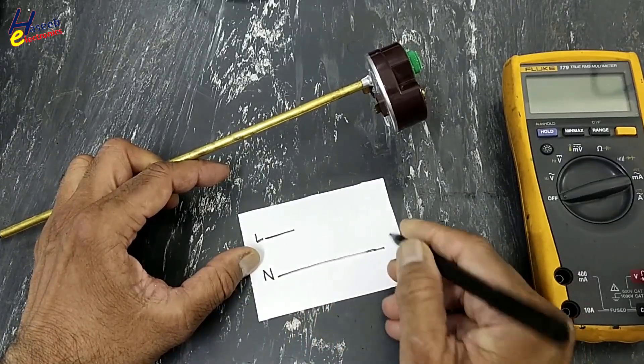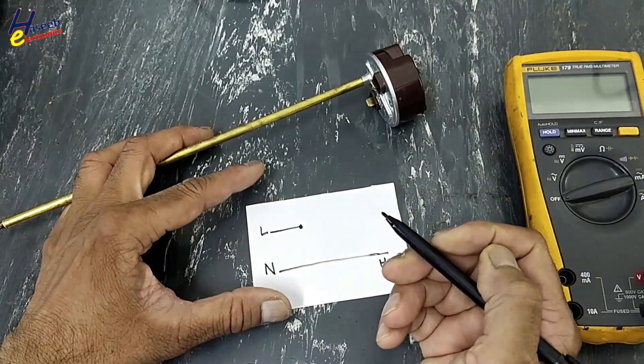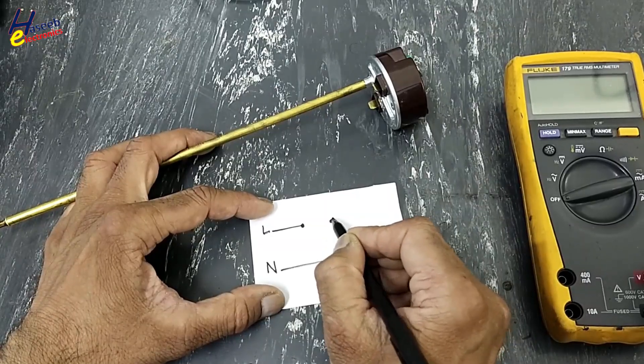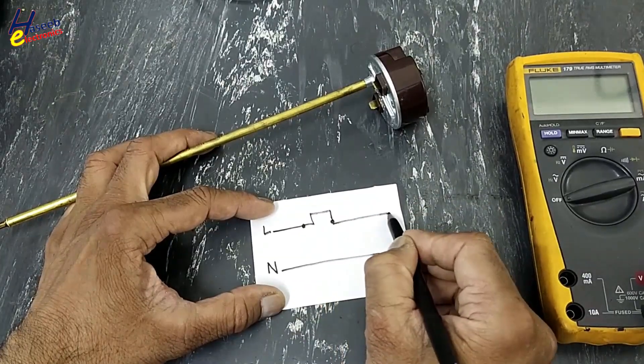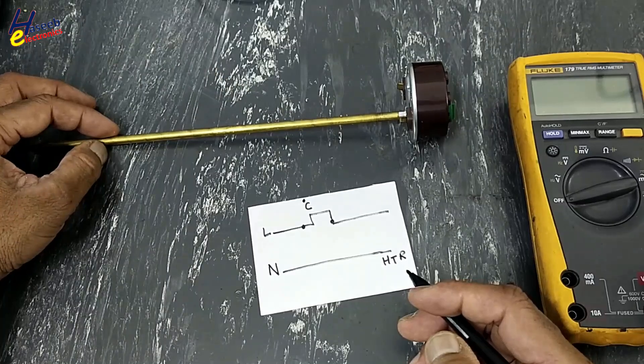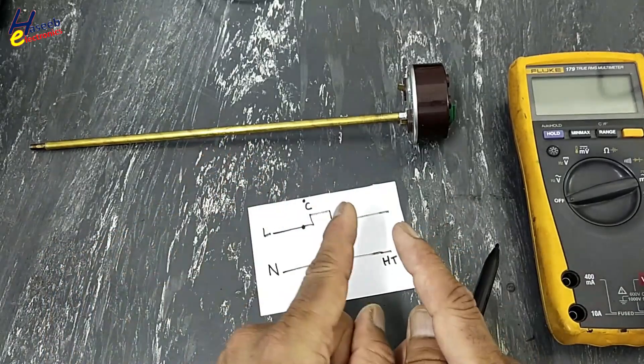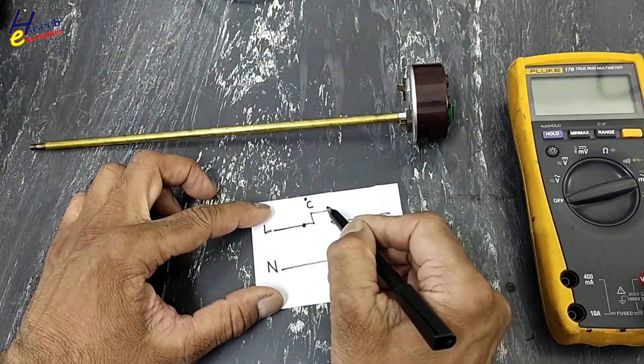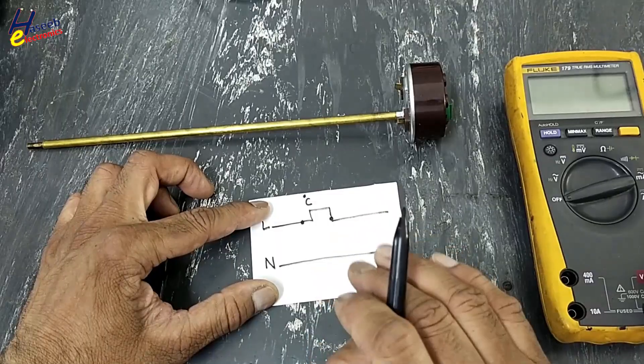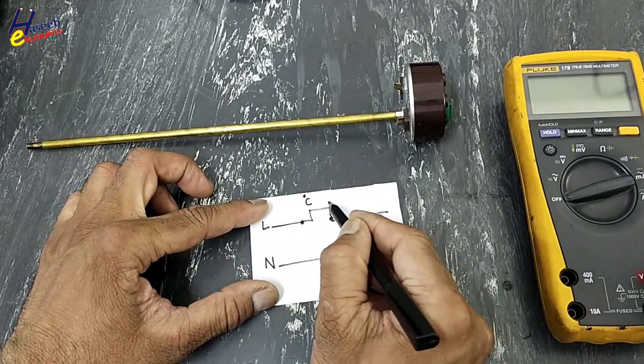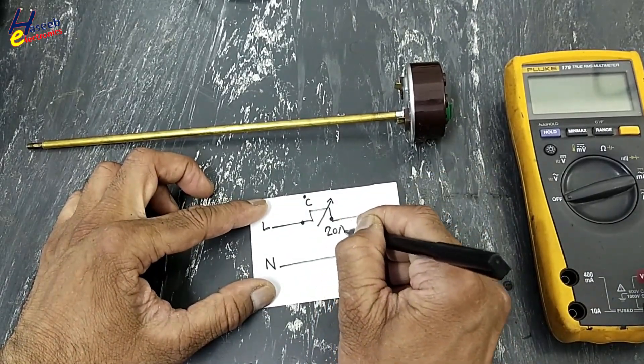But here in line terminal it is a gas-filled tube. When temperature will rise, its gas will expand and it will operate a metallic contact. So when temperature will rise it will open the circuit. If the temperature is below the specified limit it will remain on. It is adjustable. Contact rating: 20 ampere, 250 volt.